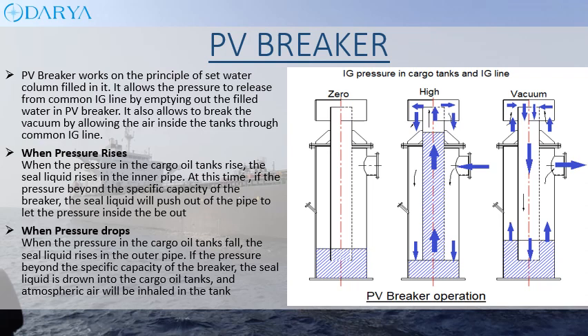When pressure rises in the cargo oil tanks, the seal liquid rises in the inner pipe. If the pressure exceeds the specific capacity of the breaker, the seal liquid will push out of the pipe to let the pressure out. When pressure drops, the seal liquid rises in the outer pipe; if the pressure drops beyond the specific capacity of the breaker, the seal liquid is drawn into the cargo oil tanks and atmospheric air will be inhaled into the tank.